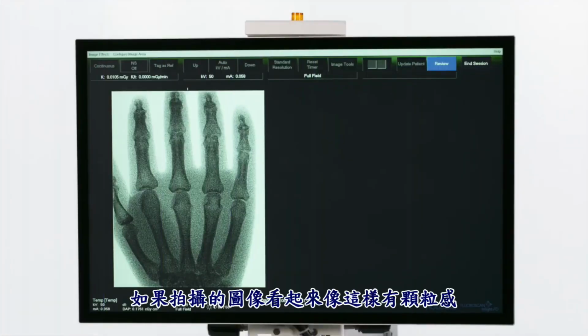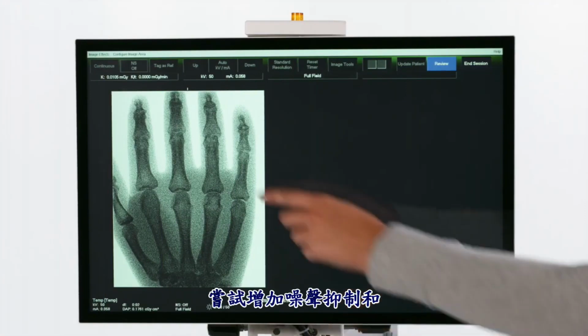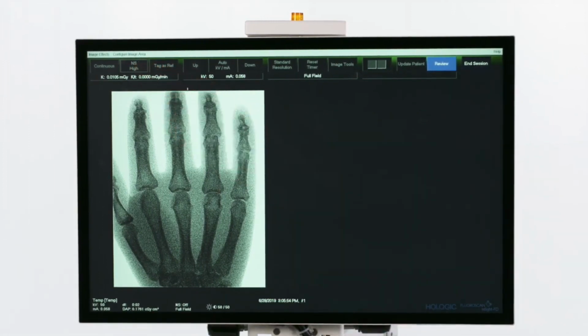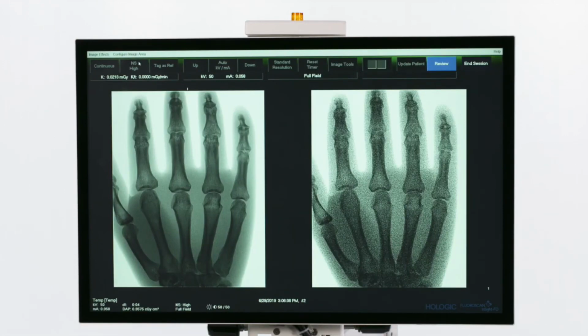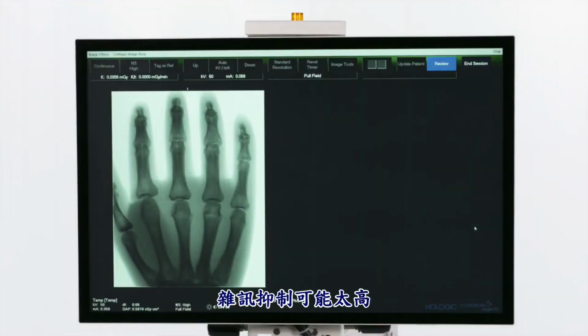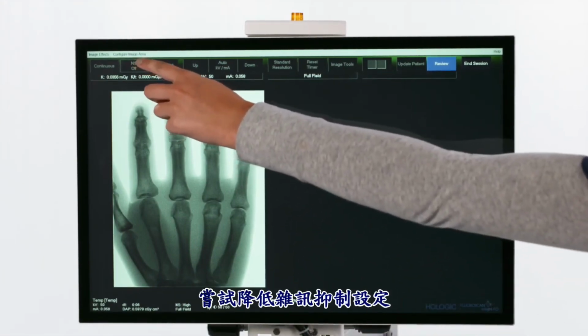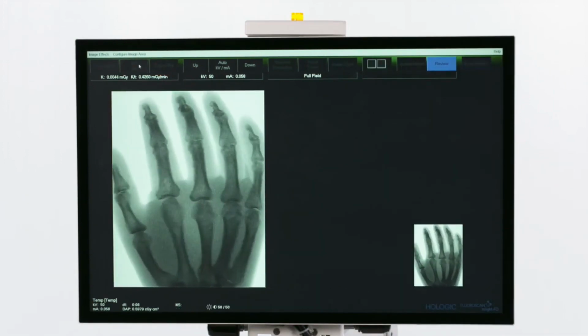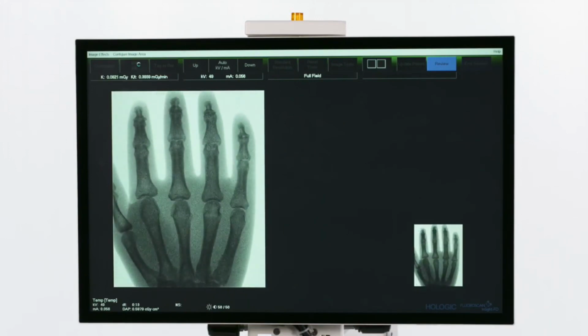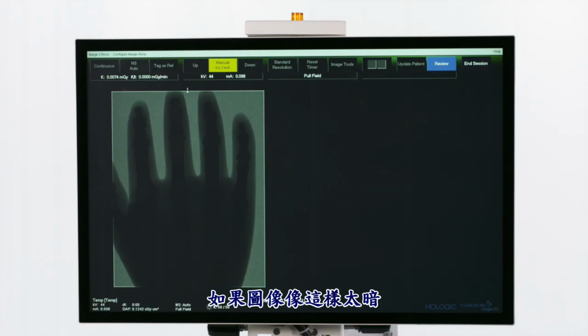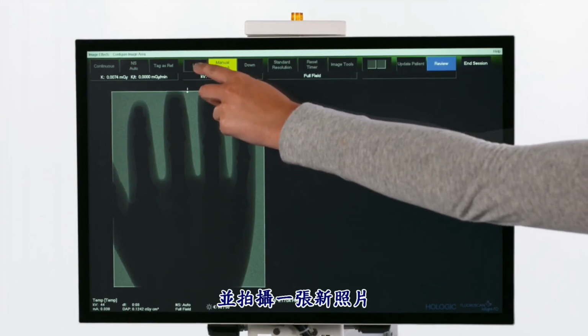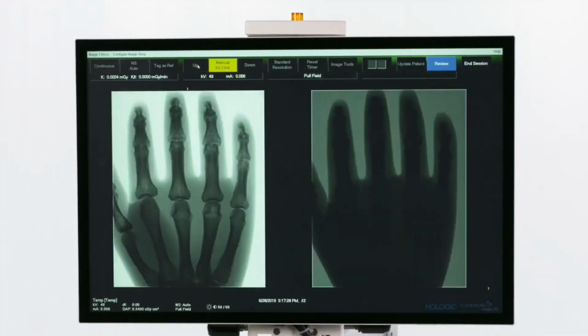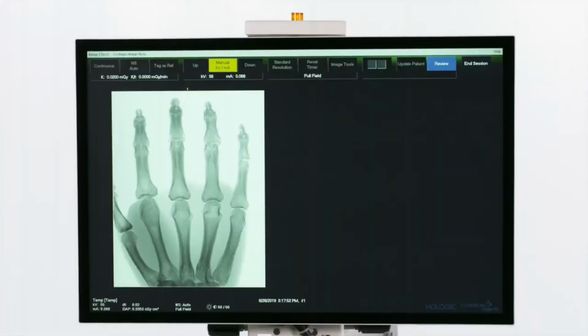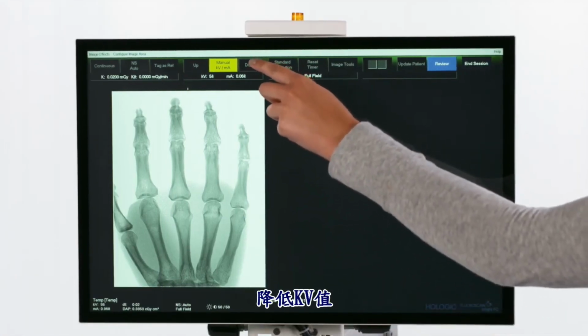If the image taken looks grainy like this, the noise suppression may be too low. Try increasing the noise suppression and take a new image. If the image taken during movement looks blurry, the noise suppression may be too high. Try lowering the noise suppression and take a new image. If the image is too dark like this, increase the kilovolts and take a new image. If it is too light like this, decrease the kilovolts and take a new image.